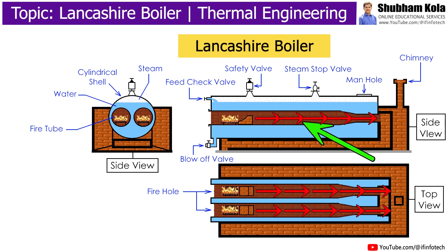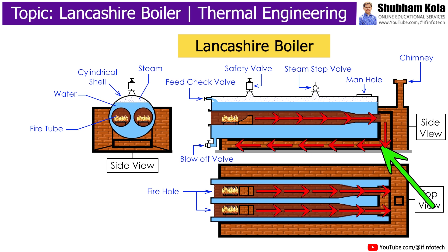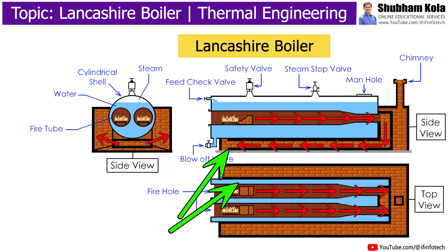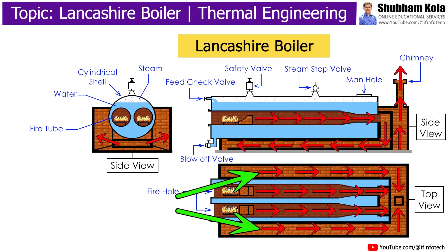Flue gases first pass through the fire tubes from one end to another, transferring 80 to 90 percent of heat to the water. The backward flue gases then pass from the bottom passage, transferring 8 to 10 percent of heat to the water. Remaining flue gases pass from the side passage, transferring 6 to 8 percent of heat to the water.